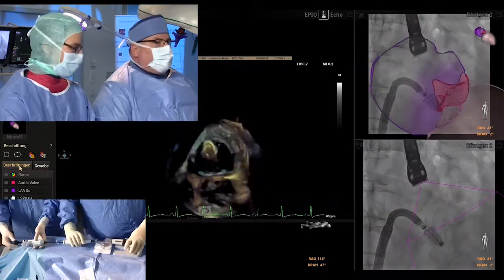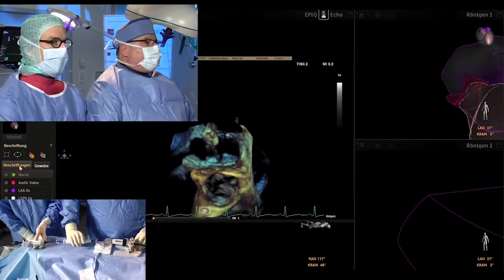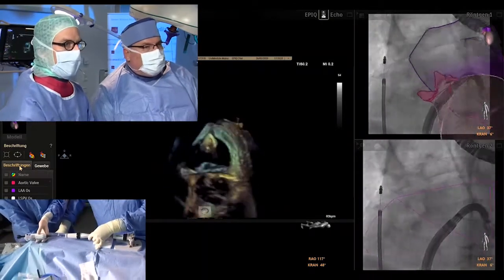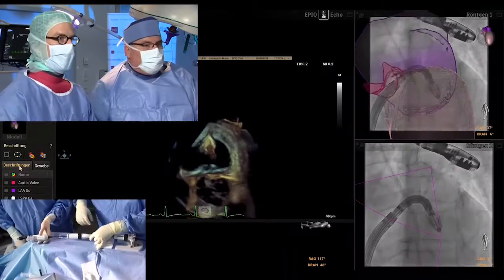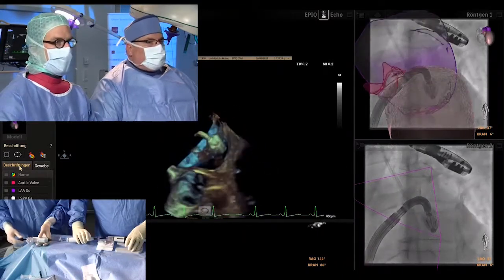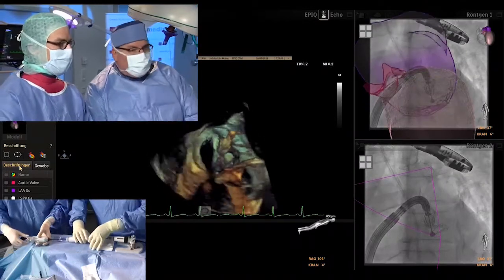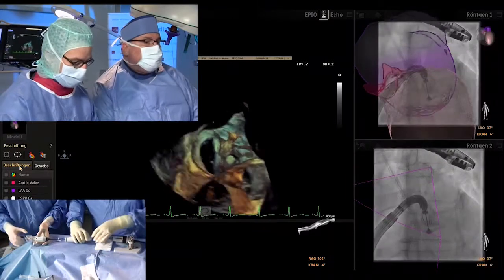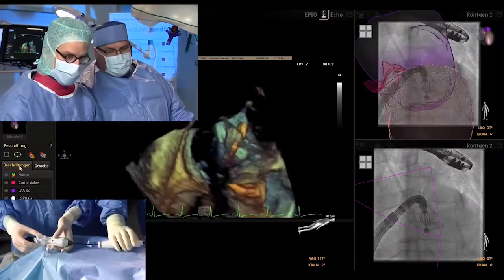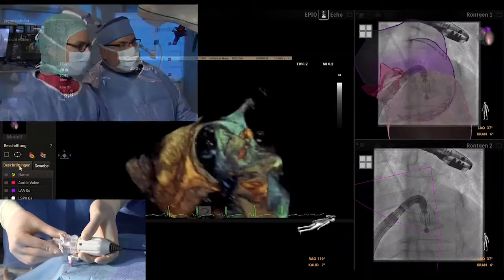Independent clasping is demonstrated: there are two sliders on the handle, one for each clasp. The security pin connecting the two clasps is removed. With the anterior clasp slider, only the anterior clasp moves; with the other slider, only the posterior clasp moves. This allows independent grasping of each leaflet — staged leaflet capture where you can address one leaflet independently of the other.